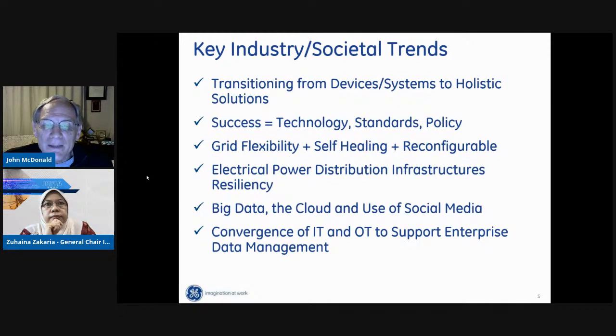So for a device, rather than a relay, let's think of a digitized substation with IEC 61850 - merging units, goose messaging for protection, process bus, things like that. Rather than a monitoring and diagnostics device on a transformer by itself, let's think of asset performance management, APM. Rather than a capacitor bank on a distribution feeder, let's think of volt-var optimization. Those are holistic solutions, not just the device. The reason is the holistic solution has much more benefit to the customer than the individual devices themselves, and because the devices have two-way communications, we can build this holistic solution.